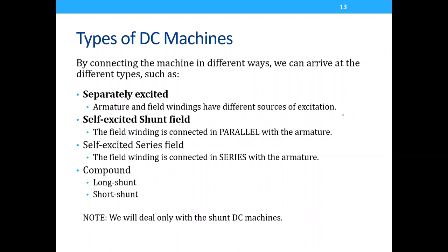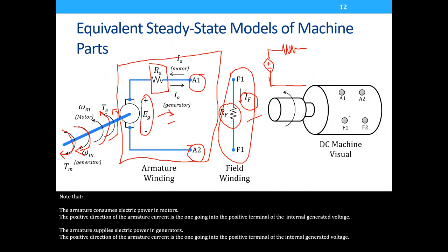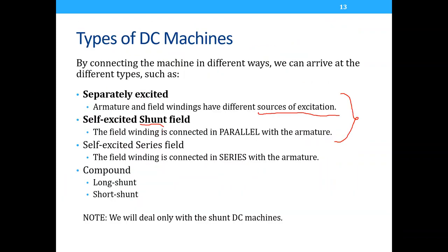There are four types of DC machines: separately excited, self-excited shunt, self-excited series, and compound. For this course, we only look at separately excited and self-excited shunt field DC machines. For separately excited, the armature and field windings have different sources — you power both separately using different DC sources. For self-excited shunt, the field winding is connected in parallel with the armature.